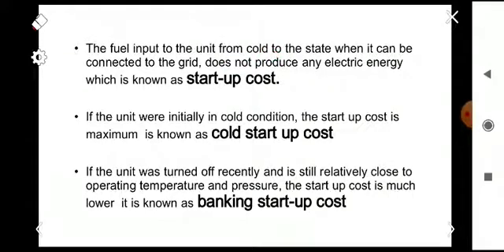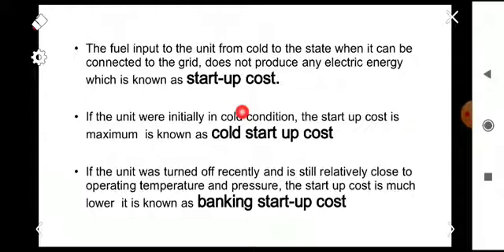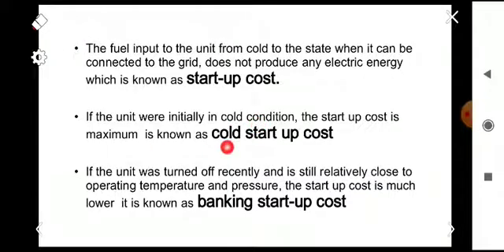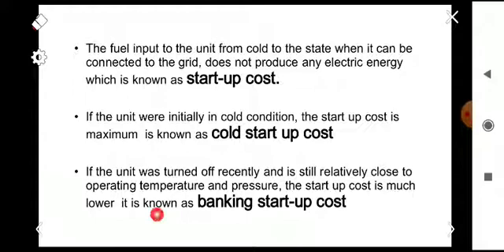A cold case means the machine has not been in operation for a long time — it is in cold mode. The fuel input from cold state to when it can be connected to the grid does not produce electric energy, which is the startup cost. If the unit was initially in cold condition, the startup cost is maximum and is called the cold startup cost. If the unit was turned off recently and is still relatively close to operating temperature and pressure, the startup cost is much lower, known as the banking startup cost.